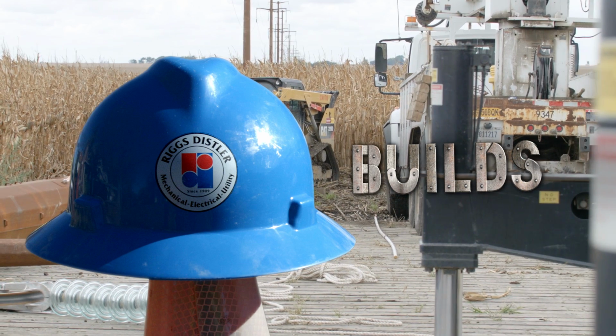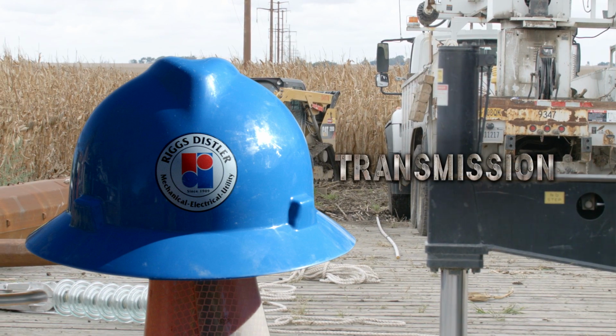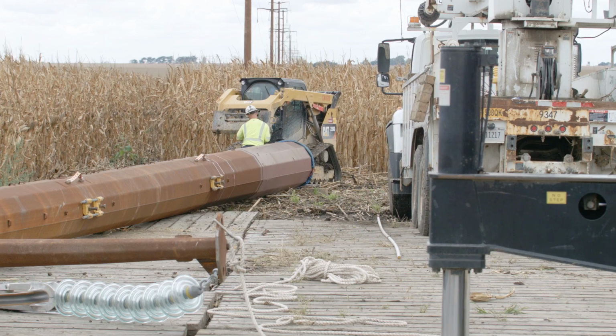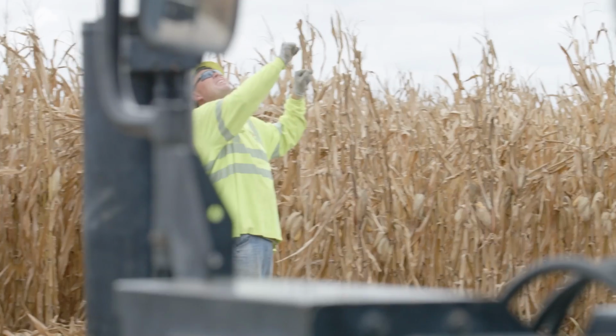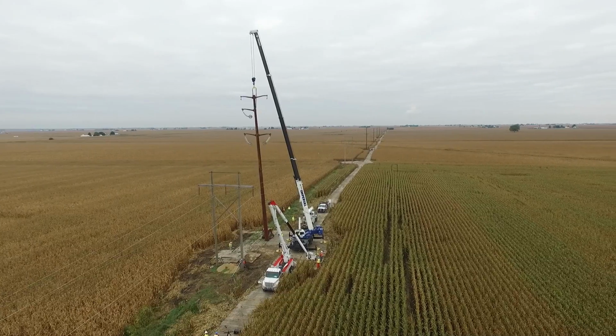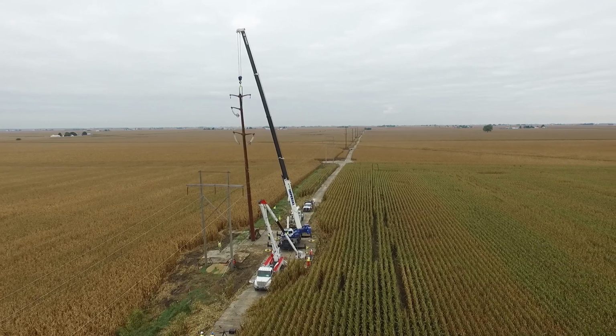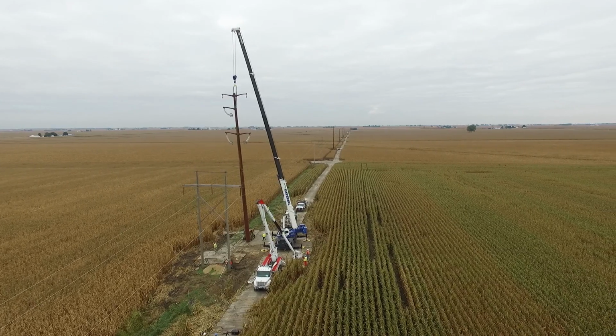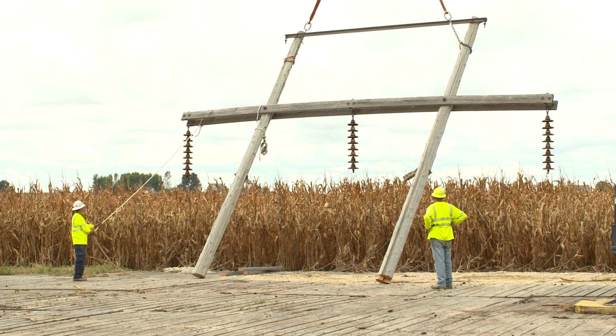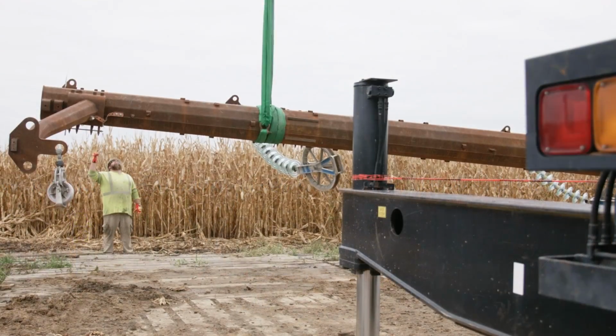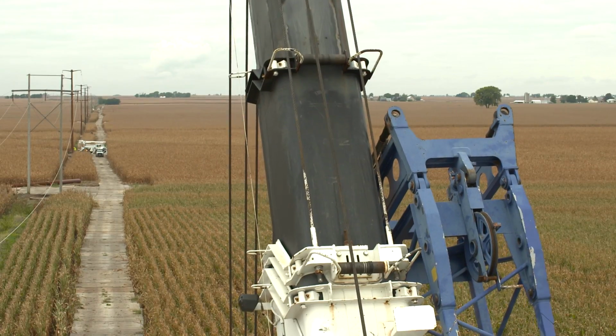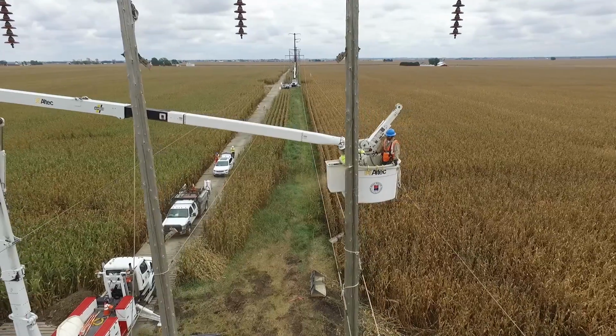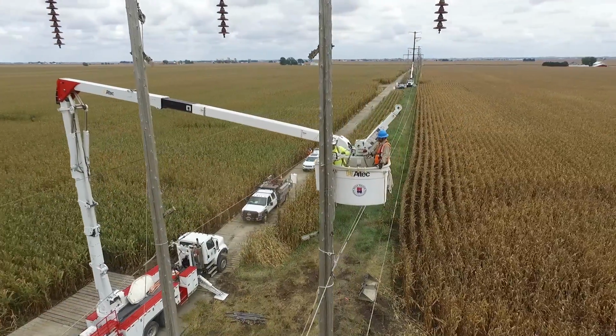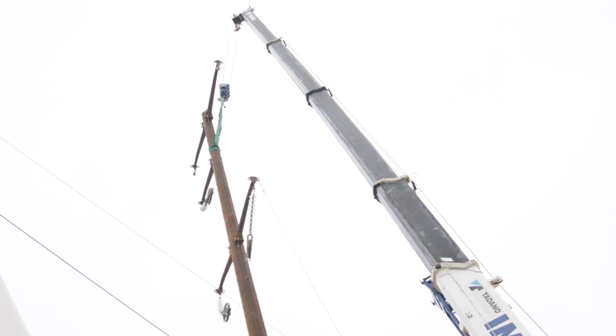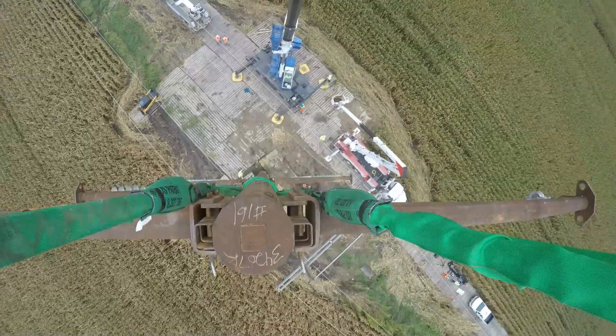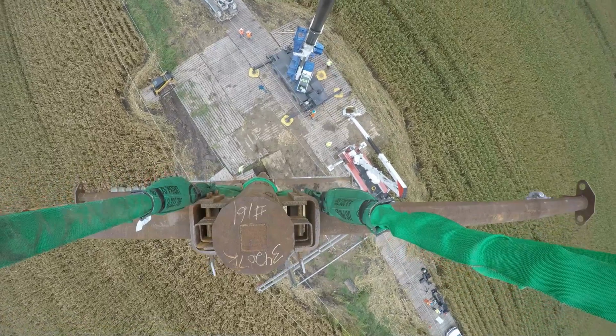Hi, I'm Scott Sematitis, Operations Manager of the Transmission Lines and Special Projects Group at Riggs Distler. The L10714 transmission project is a 26-mile rebuild of an existing 138 kV transmission line for a customer in Illinois. A rebuild means tearing out all existing structures and wire and rebuilding with all new structures and wire. For the L10714 project, we removed 216 existing wooden H-frame structures and replaced them with 214 multi-section steel poles. The new poles range from 85 to 120 feet in height.